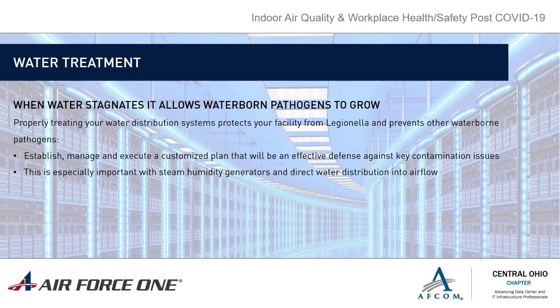Brian, you got anything? Well, specifically in the data center world, there's a lot of humidity or steam humidity generators. It's important to make sure that water is treated, the RO systems are working as they're supposed to, and you're not putting contaminated water or moisture into your space. One recommendation was maintaining humidity, which lands right at where most data centers want to run, between 40 and 60 percent, 60 being a little high, 40 a little low, 50% being the midpoint. Maintaining that 50% helps keep a cleaner air environment, specifically with COVID.